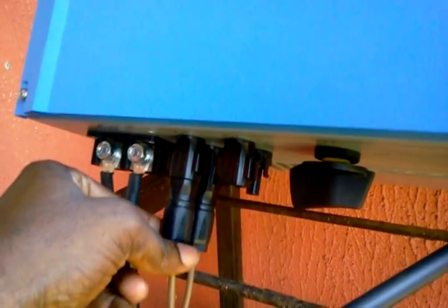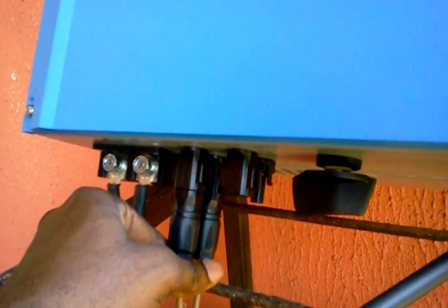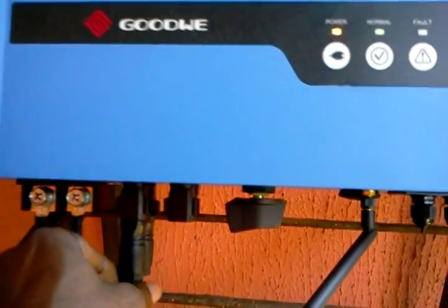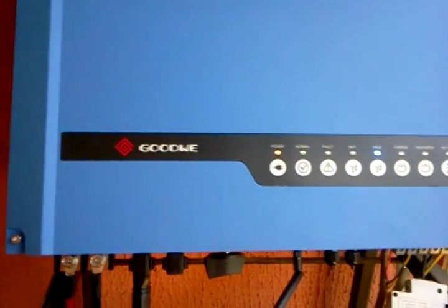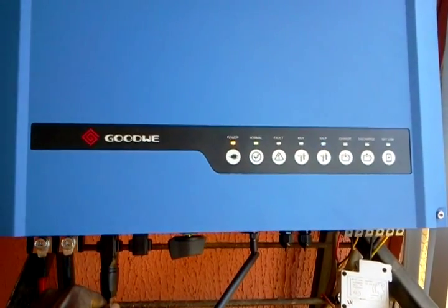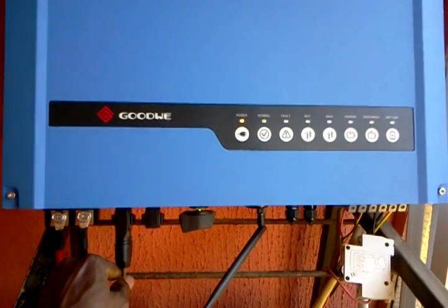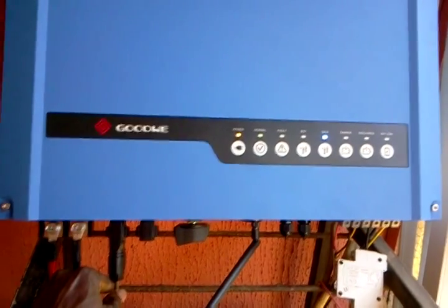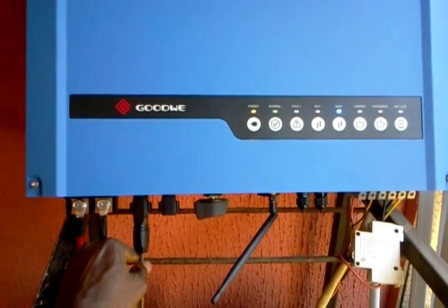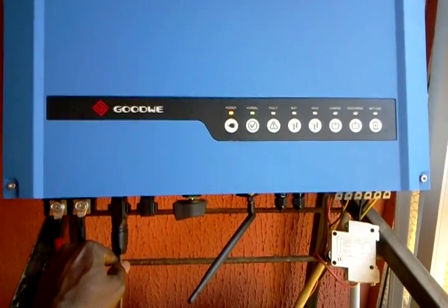These are the PV connectors for the positive and negative from the PV string. I have a string of five solar panels connected in series. One beautiful thing about the GoodWe solar inverter is that you can string together as many panels as possible, up to a maximum of about 500 volts. The advantage of this is that you can have high voltage and very low current, which saves you on the gauge of cables running from the solar panels down to the inverter.